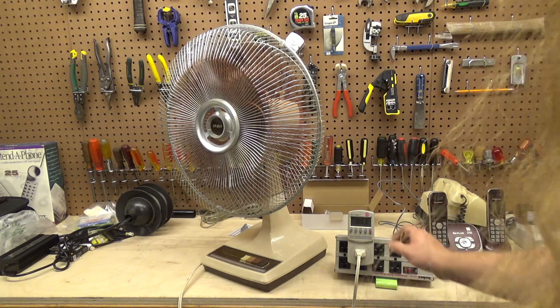It just seems really sluggish to me. That's 0.71 amps, 74 watts, with a power factor of 0.87. High speed is pulling 0.88 amps — 84 watts with a power factor of 0.81, which is pretty poor for a PSC motor. It should be well into the 0.9s, and we're only getting 0.81. So it's drawing 0.85 amps, which is not far off from the rating of 0.9, but the power factor doesn't seem right to me.